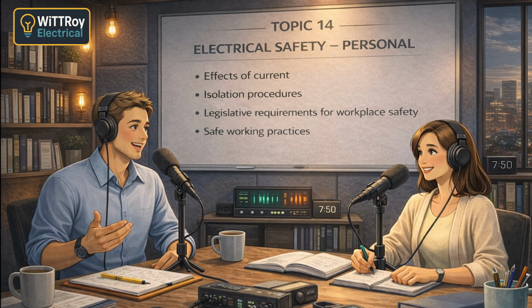Okay, so how do we stop that risk? We use isolation. Isolation removes the electrical energy so the circuit cannot be energized while work is being done. Is switching off the same as isolation? No, switching off alone isn't safe. Someone could turn it back on. Isolation means physically disconnecting the supply and securing it. That's where lock-off comes in. Correct. Locking off means securing the isolator in the off position using a lock so it cannot be operated.